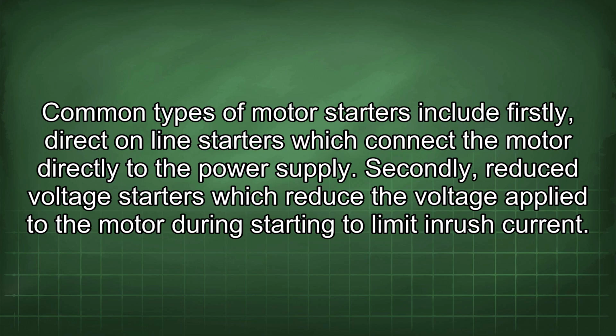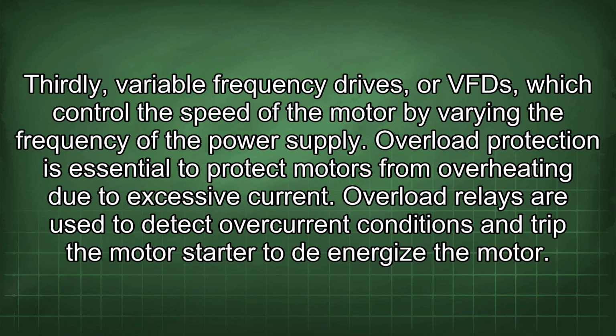Secondly, reduced voltage starters, which reduce the voltage applied to the motor during starting to limit inrush current. Thirdly, variable frequency drives, or VFDs, which control the speed of the motor by varying the frequency of the power supply. Overload protection is essential to protect motors from overheating due to excessive current. Overload relays are used to detect overcurrent conditions and trip the motor starter to de-energize the motor.